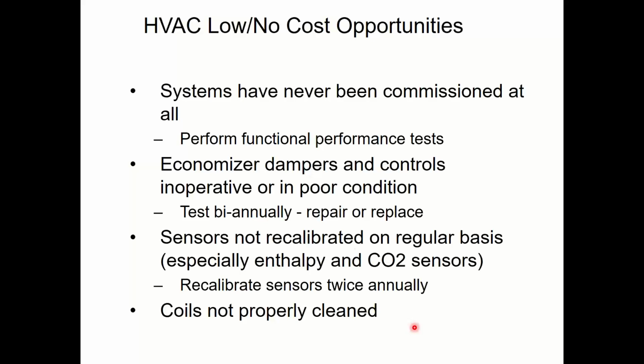Somebody asked, Mike asked, how often you should clean the coils. That's an excellent question, and there's no singular answer. It's going to be dependent on what's building up on the coil. So that's going to be dependent on a couple different factors. The main factors involved are going to be how good are your filters, how tight are your filters in the cabinet, meaning can airflow get around them, right?